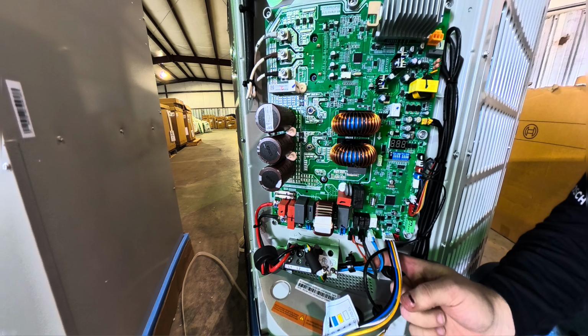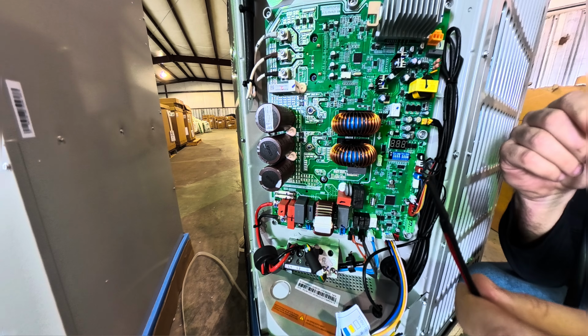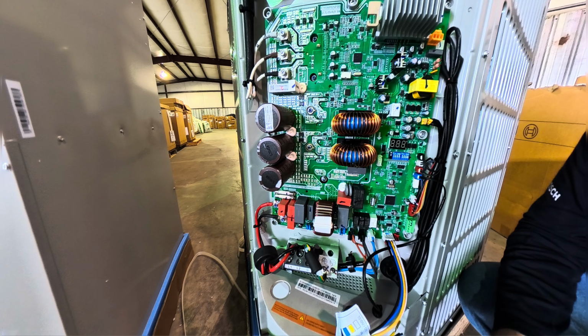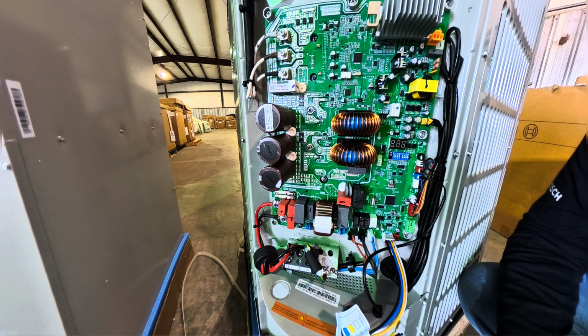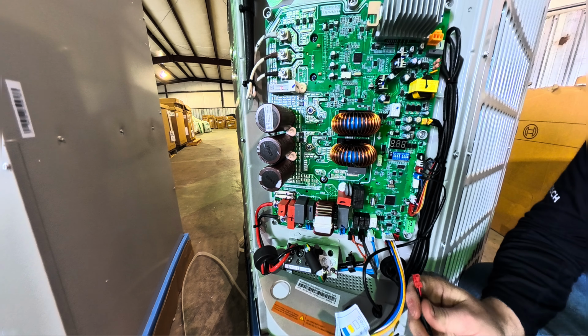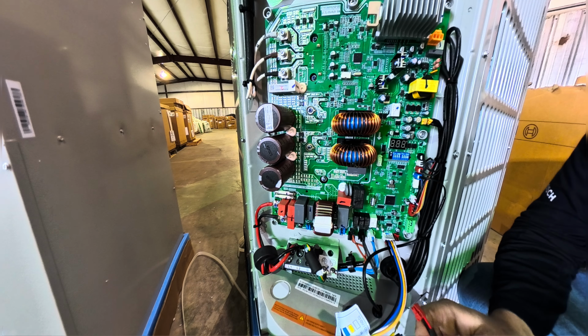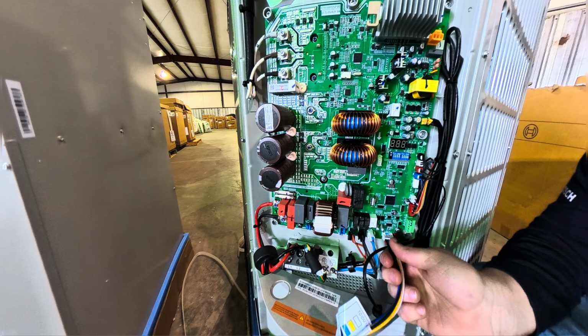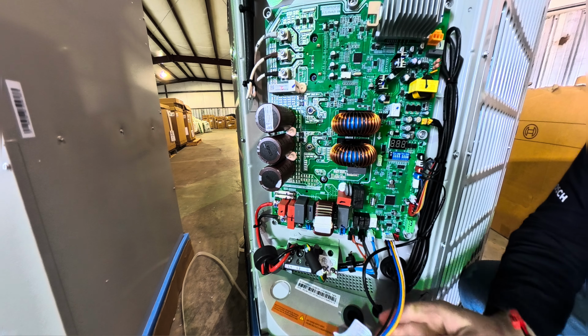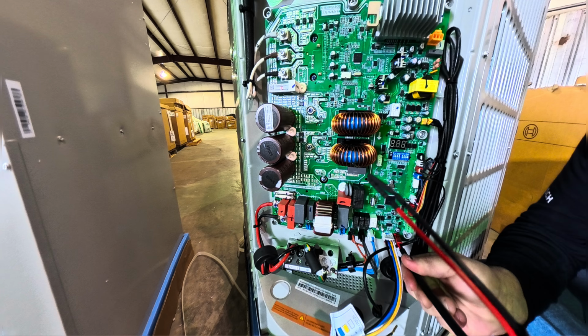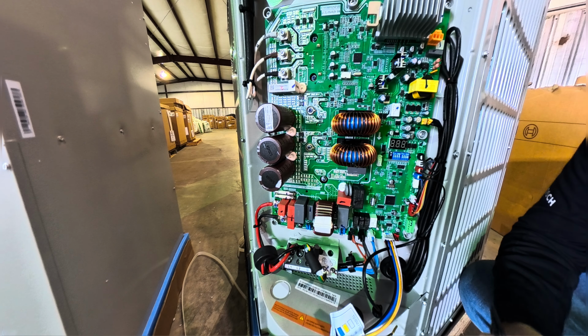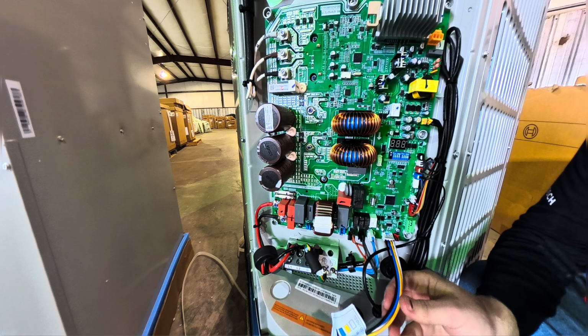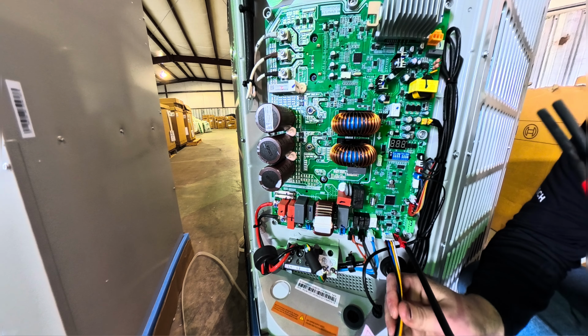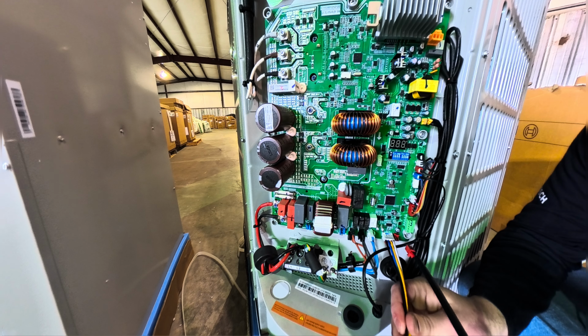But if we were to pair this with a 20 SEER air handler, it also comes with this 2-wire whip. So we can pair it with a 20 SEER air handler and wire it non-communicating if we want to. Or we can wire it communicating for some extra dehumidification. All you're going to have to do is unclip your thermostat wires, clip in the communication wires, and wire it that way. You don't want both of these hooked up at the same time. It will fry this control board. Don't hook up both communication and thermostat wires. One or the other. You got to choose.